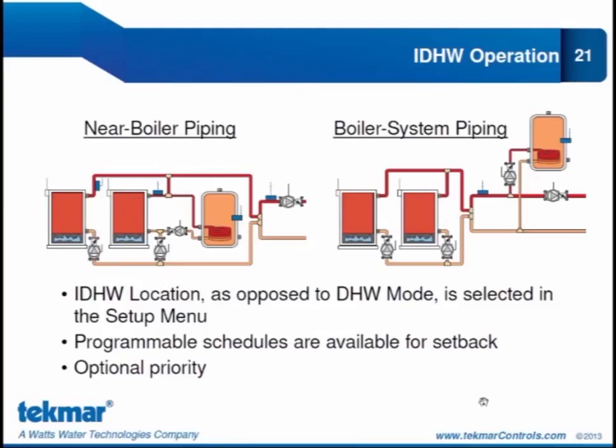So what we've done in the 284 is change that. Now we are not going to use modes. We're going to require you to enter the location. So is the indirect domestic hot water piped near the boiler, or is it on the boiler system side? You select the location. So it's very intuitive. If someone else, other than the person who set it up, is now trying to service or make any adjustments to the control, it's very easy for them to see how it's been configured.